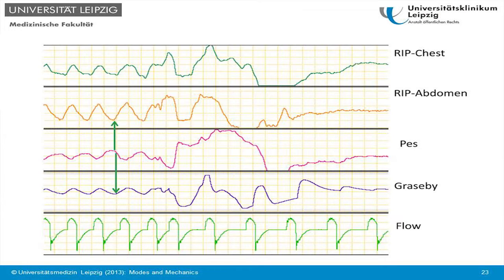So how do these things work? Here's a reading of rib band readouts. This is esophageal pressure, and we see that this is a Graseby capsule, and this is the flow. And we see that when the esophageal pressure falls, which means the diaphragm of the patient is contracting and the patient is initiating a breath, we are getting a pretty fast pressure drop, also a pressure rise in the Graseby capsule. So it's about simultaneously, and also the rib band, they are about the same speed in determining that the patient is initiating a breath. So this seems to work pretty well.